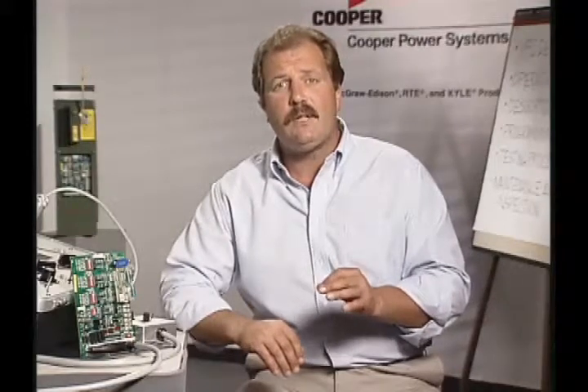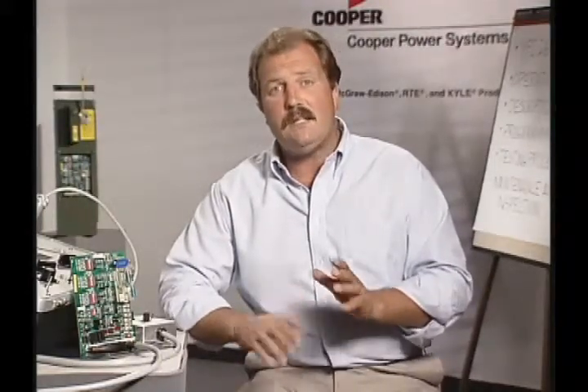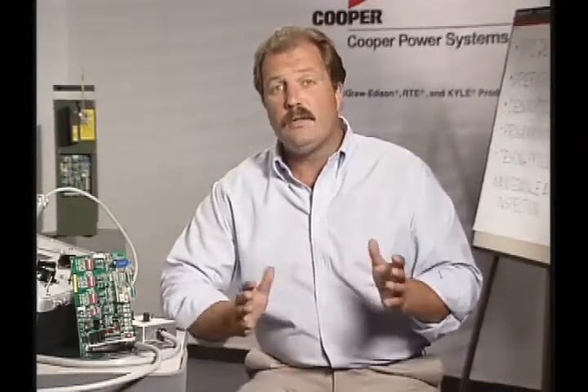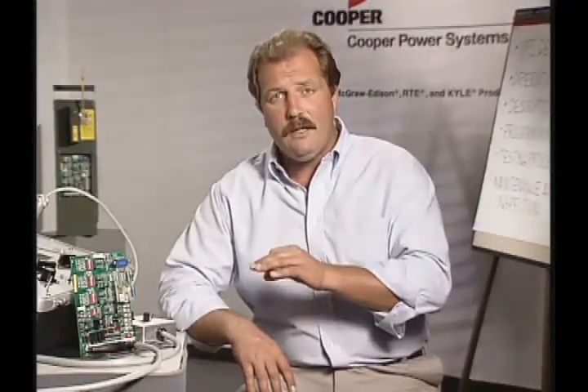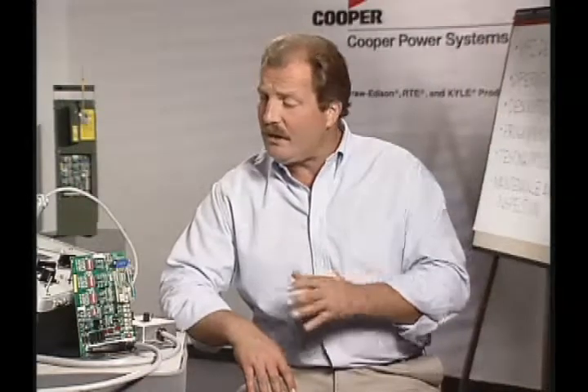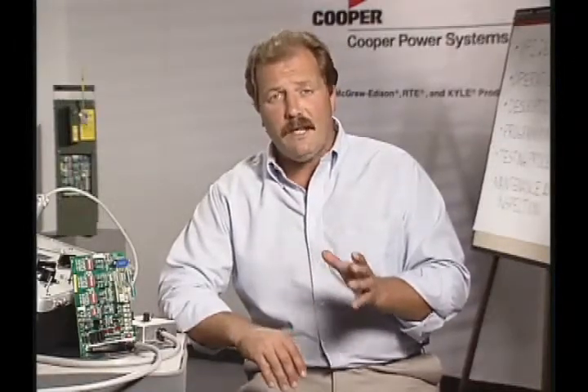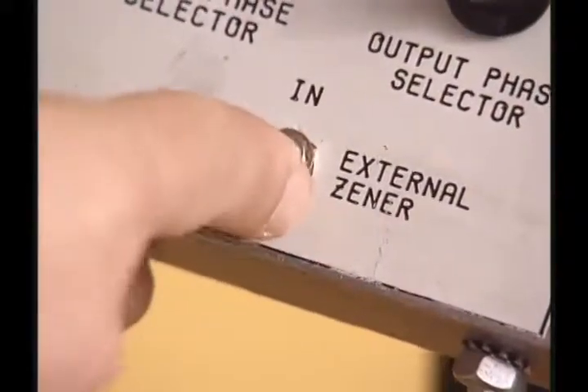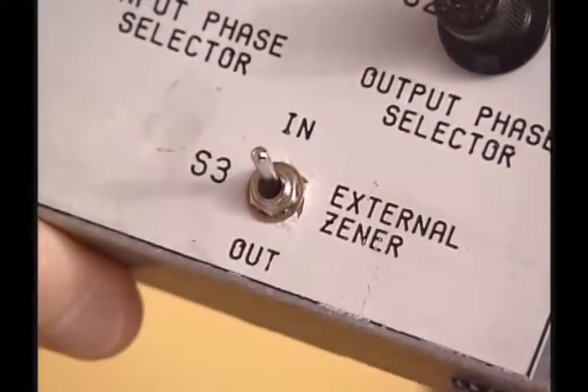The time delay trip test verifies that the time delay circuit is functioning. The ETC tester is first calibrated to deliver a fixed value of fault current to the control. The control should then respond with a trip signal. The time delay between the application of current and the receipt of the trip signal is recorded on the ETC time display. To test time delay trip, follow the same tester setup procedures as in the minimum trip test, except the adapter cable Zener switch must be moved to the in position.